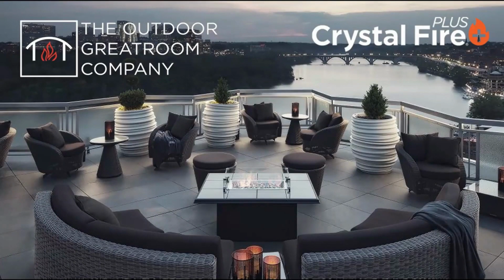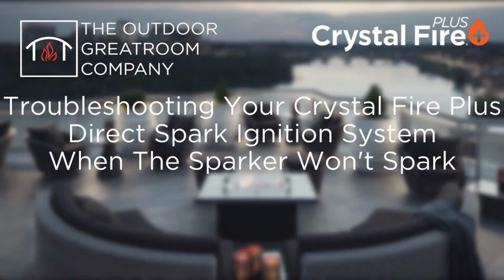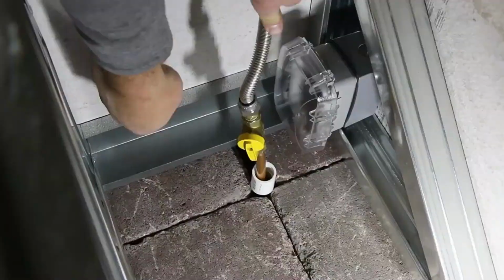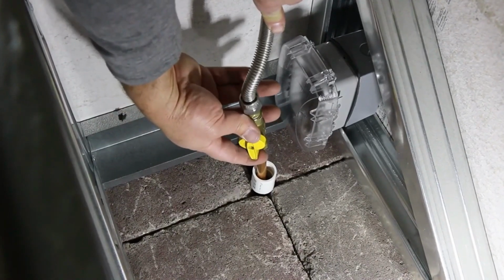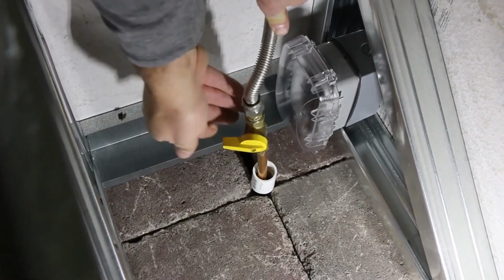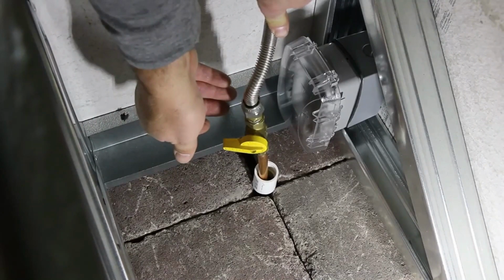Hello, this short video will help you troubleshoot your Crystal Fire Plus direct spark ignition system when your symptom is the sparker won't spark. Follow these steps. Note, it is always a best practice to shut off the gas line leading to the burner to assure you do not accidentally turn on the flame while troubleshooting for spark.